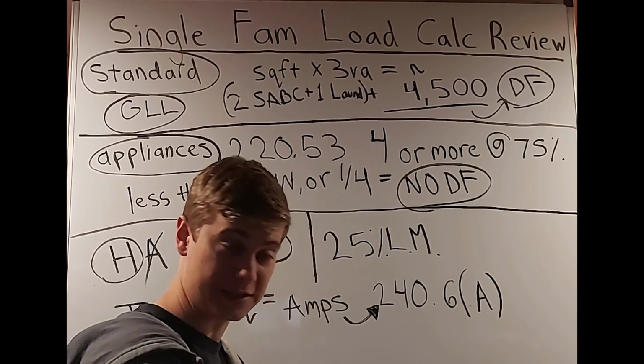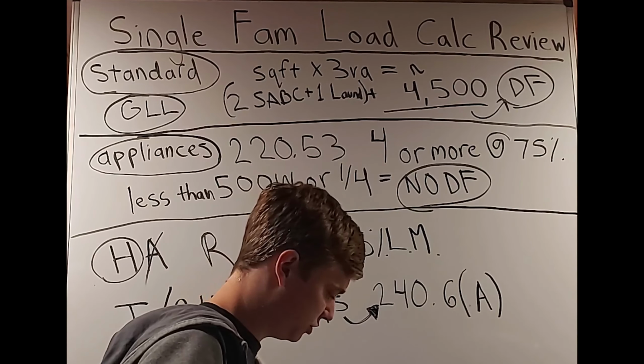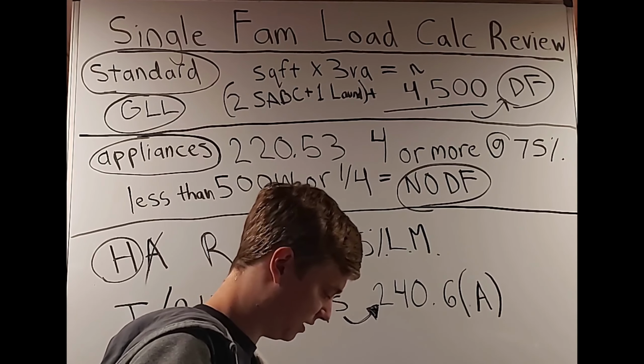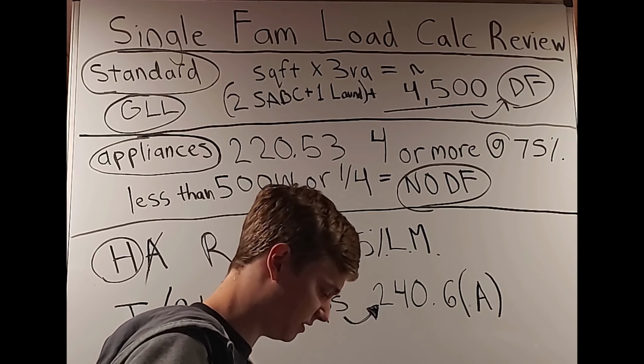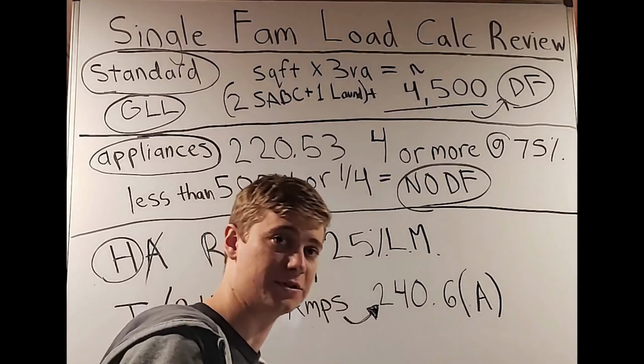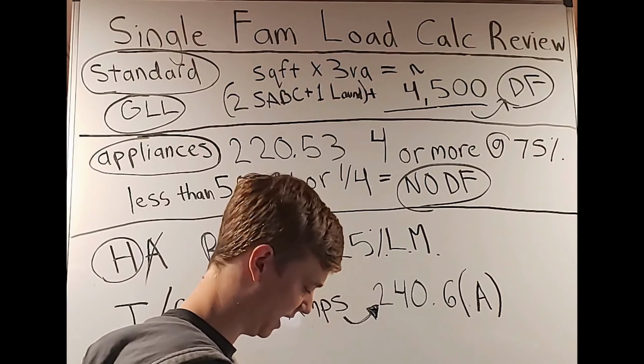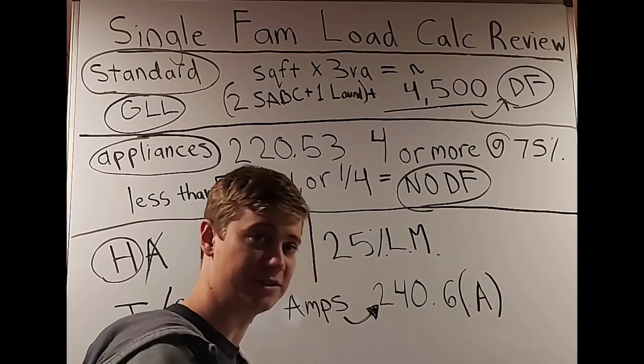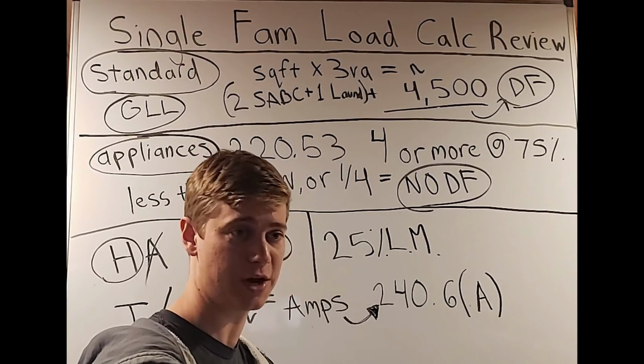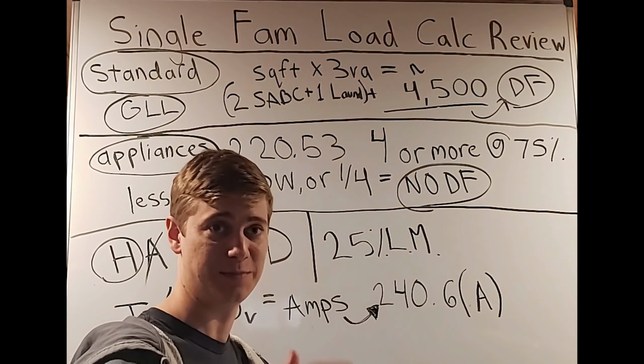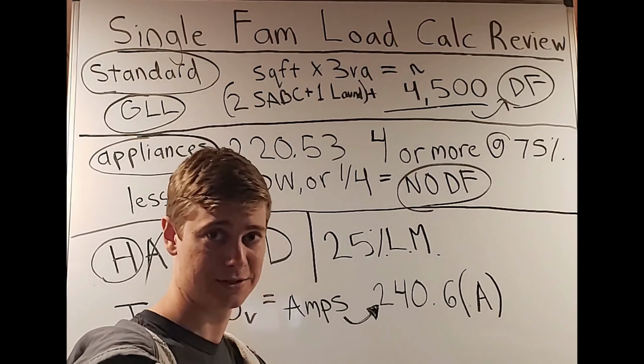And you normally do this, but it's good to know Article 240.4b, which tells you that basically if it's 800 amperes or less, you're going to do that. And in other words, you're going to round up to the next bigger size of breaker, unless that next bigger size is 800 amps or bigger than that.